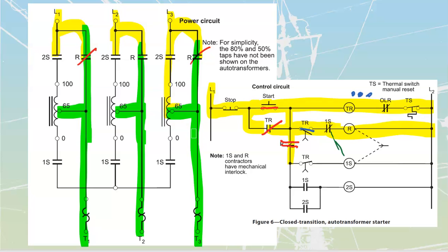It's a completely closed connection going through that is always, always, always going to maintain my flux at the motor. We never once have the motor itself lose power, so we don't get that little bit of a torque dip or any type of line disturbance off of it. Really cool set of autotransformers.